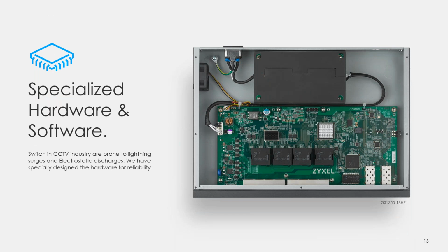The hardware is made very robust, so especially the surge protection has been improved 4 times. The switch, of course, is grounded through the power socket itself, but you also have an additional grounding screw on the back of the device where you can ground the device to, for example, the rack or a grounding block of some sort.